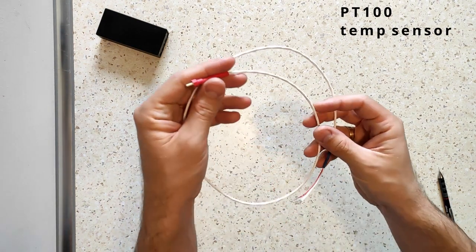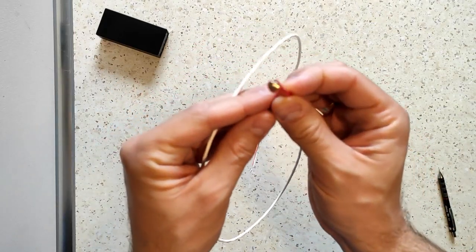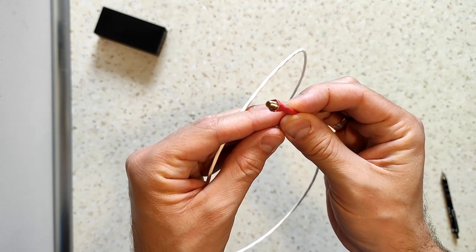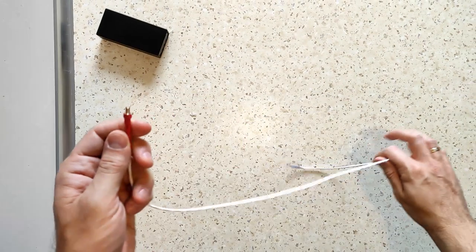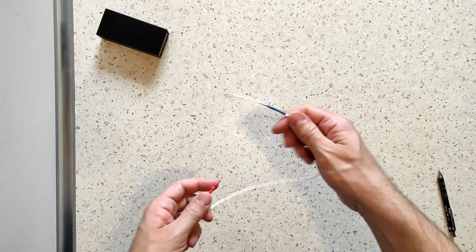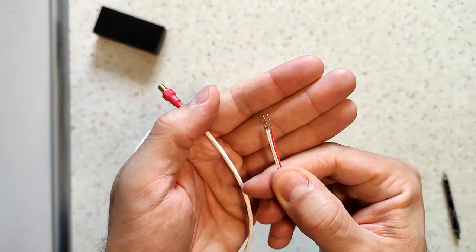You're also gonna need the temperature sensor. This one is of PT100 variety and has a threaded probe. This is M4 threading, which is great. It will thread right into the boiler where the original thermostat is located. The sensor features 3 wires: one for signal, two for shielding.